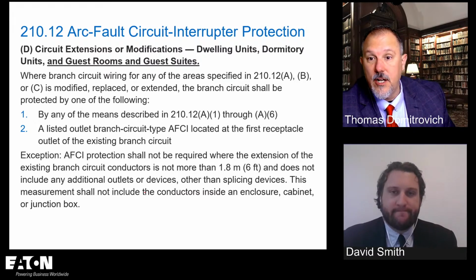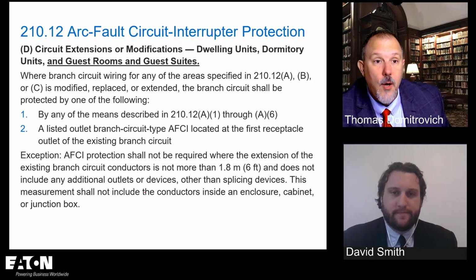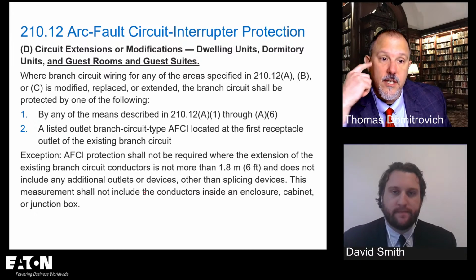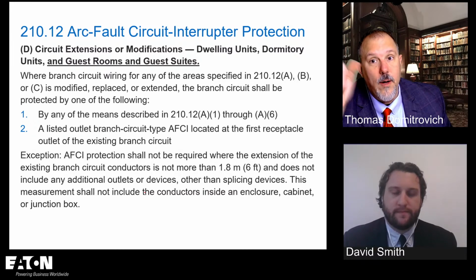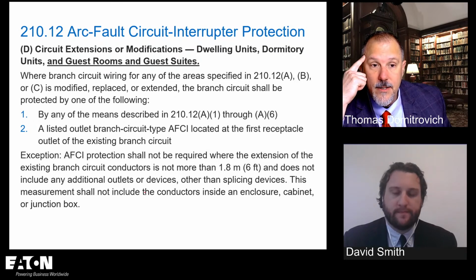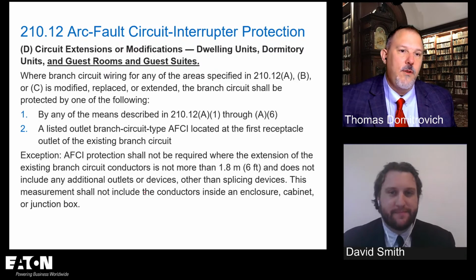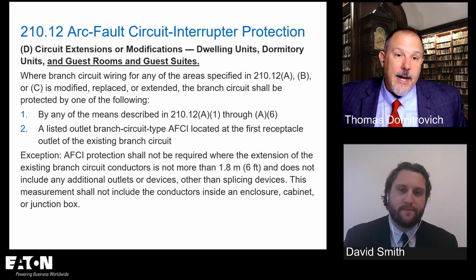And then if it's an existing one, you change a receptacle out, are you pulling a permit? No. Right? You're relying on the conscientious electrician who's going to say, oh, I have to put an AFCI receptacle here. The chances of that happening... I just get frustrated with 210.12(D). I really do. I know the intent of it.